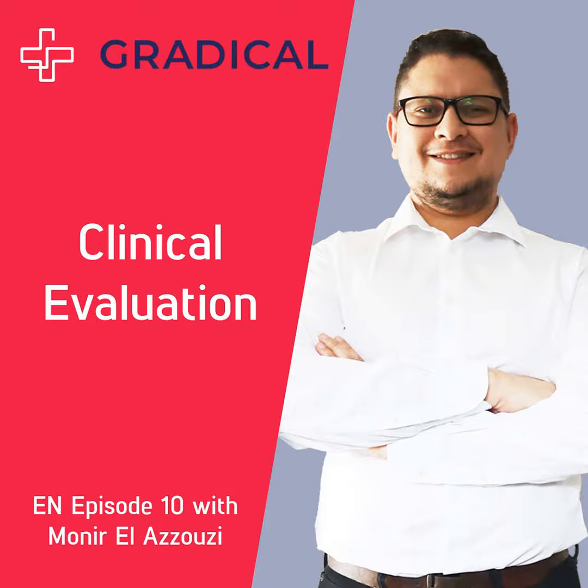So no, you have to do. So we have two aspects. We have the preclinical study and the clinical study. The preclinical studies are the studies that you are doing in laboratories, animal studies, for example, or bench tests that you are doing in the laboratories or whatever. To prove clinically that your device is fine, there are 3 stages.